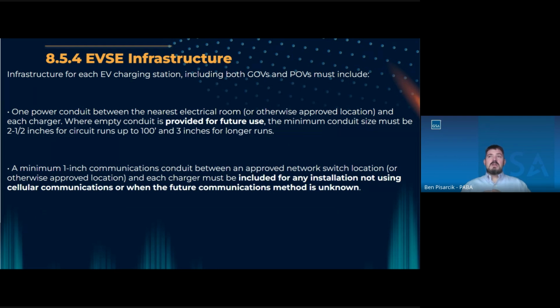Those conduits are much larger than what would typically be needed, but we don't know what we're going to run into in the future, how many chargers may share that conduit, and we increase the size due to voltage drop and for those reasons. So we've had folks come to us and say, we know exactly what we're installing. Do we still have to install a 2.5 inch conduit? And that's not the case. We've allowed them to install what they need because they know what they're installing at that point. I put in bold here, this is for future. So we make sure we're protected in the future. We have what we need in the ground.